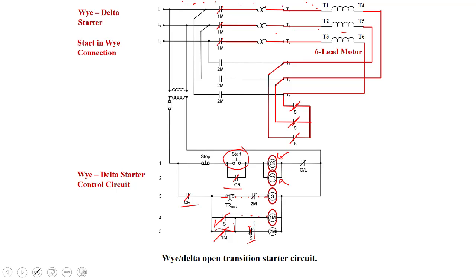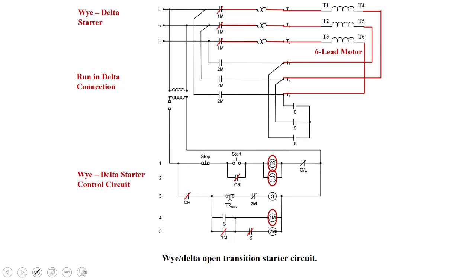So what happens when the timer de-energizes? Well, in run, we're going to go to delta. The timer opens up right there, so that would open up. That means the S coil would de-energize. When the S coil de-energizes, this would go back to open, but we still have a holding circuit here. So 1M stays energized, and the S contact here that was open for us now goes to the closed position. So 2M will energize.